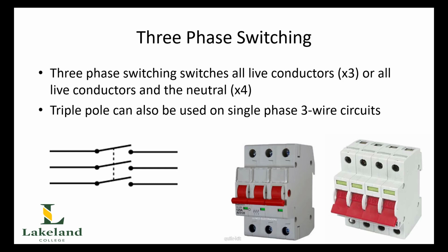Now, even though the photograph I have on screen here are of circuit breakers, MCBs, miniature circuit breakers, it's important to realise that circuit breakers, or indeed any circuit protective device, should not be used for switching. It should be used for isolation and fault protection only. In other words, you don't go home and turn your lights on in your house by turning on the circuit breaker.